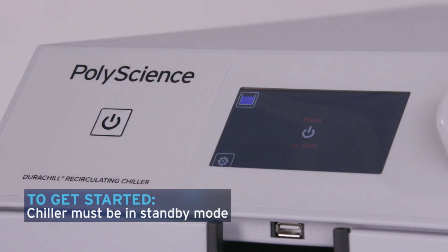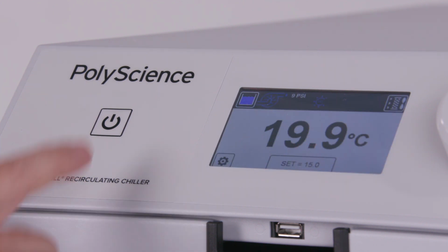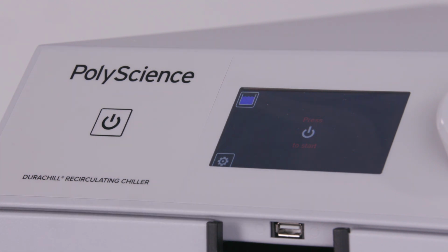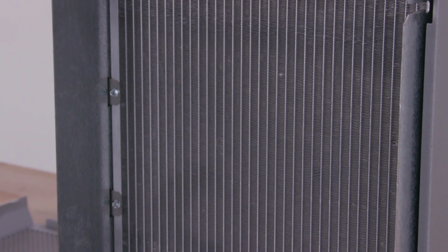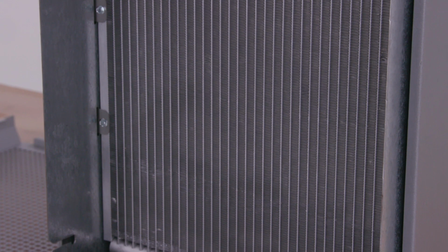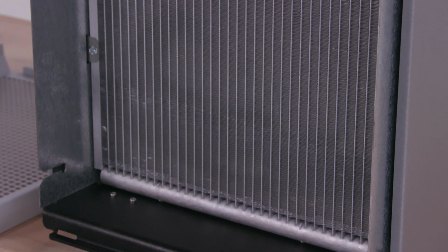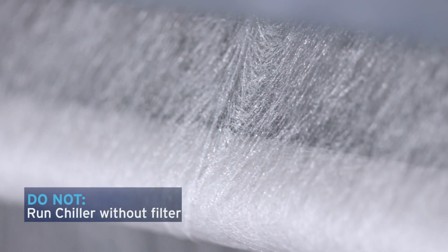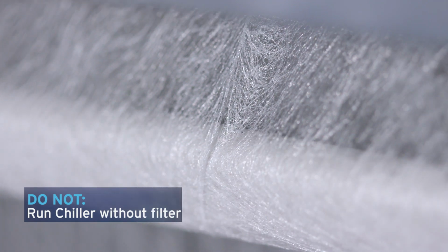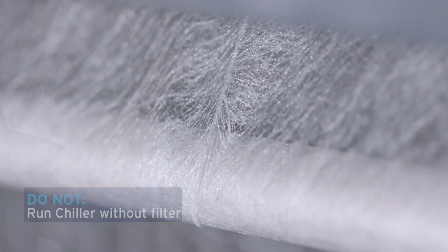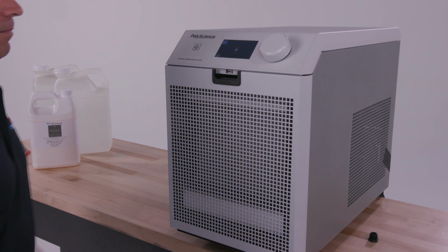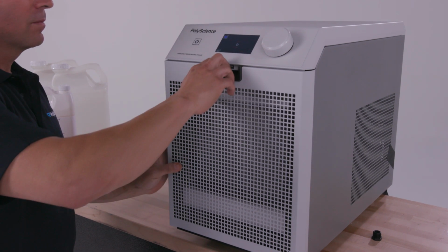To get started, make sure your chiller is in standby mode. If it's running, press the power button to the left of the screen to turn the chiller off. If you remove the air filter with the chiller running, an alarm will sound indicating no air filter was installed. It's never a good idea to run your chiller without an air filter, as it lets dust and contaminants into the condenser.